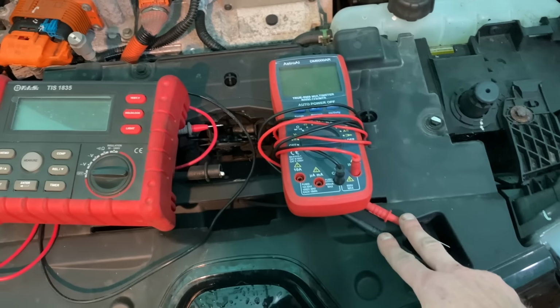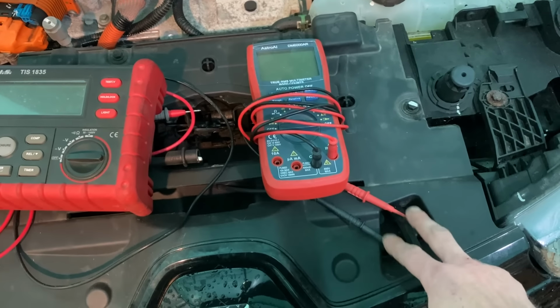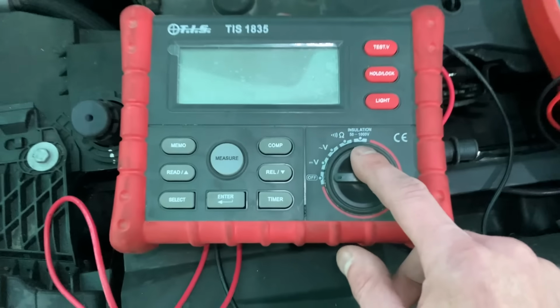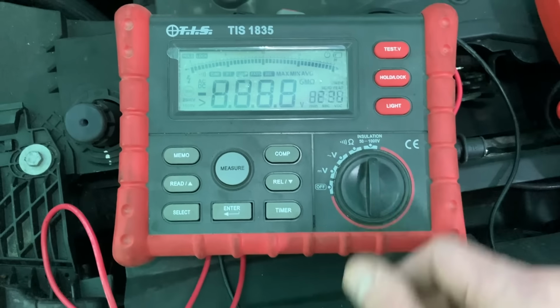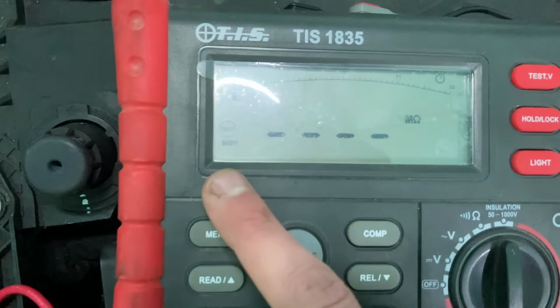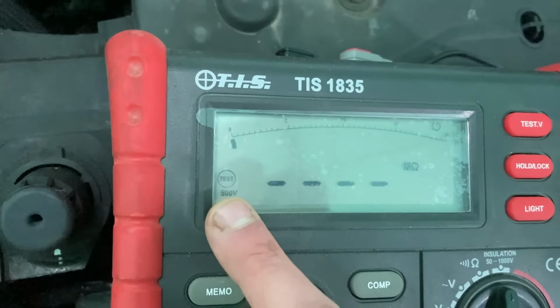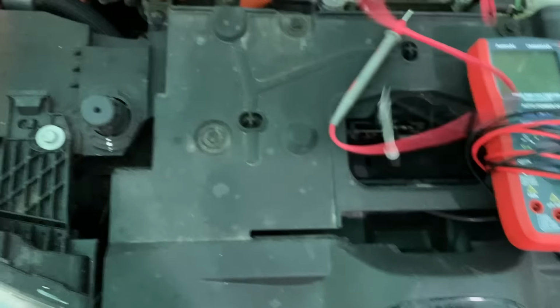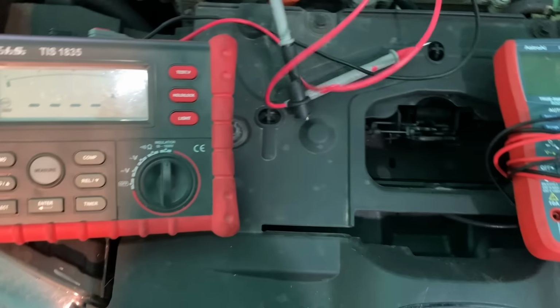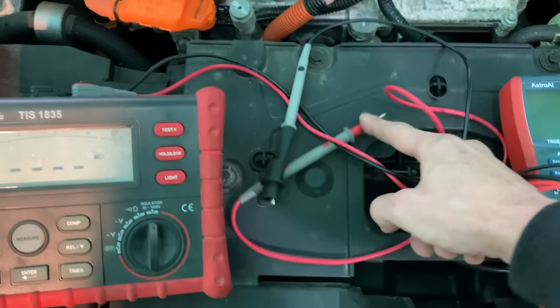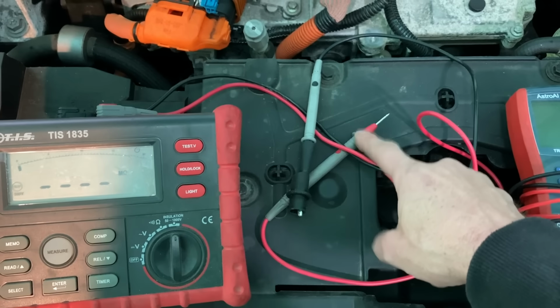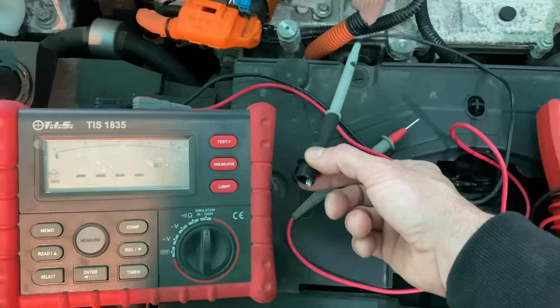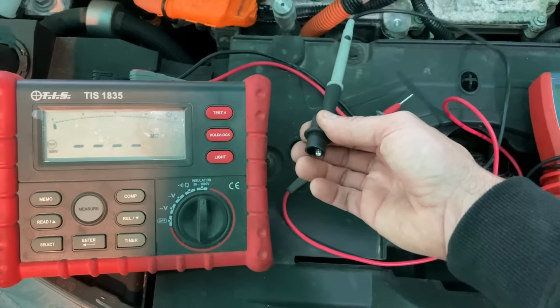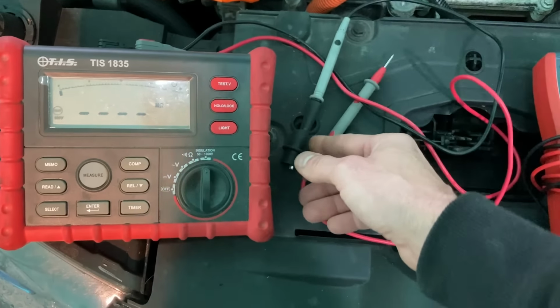If we did a normal resistance test, you'd have absolutely millivolts on here, tiny amounts. Whereas with this machine you can see we've got 500 to 1000 volts. If we click that on, I've got it set to 500 volts. So what that actually means: I've still got 2 leads, but on this red probe the machine will generate 500 volts, and then it will try to work out whether that is reaching this lead. So it should be totally isolated.